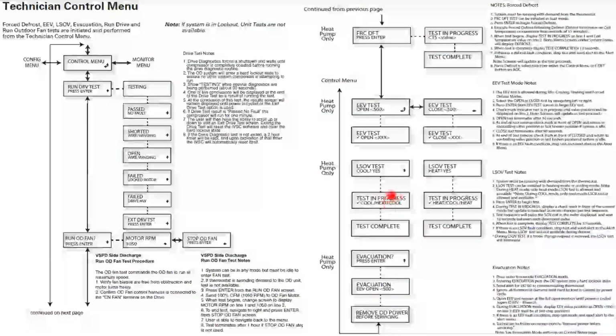And then it'll display test in progress, test complete. If we have to do a pump down and get the refrigerant back into the compressor by closing the liquid line and pulling all that refrigerant back in, we can do that. What it's going to do is open all the EEVs, including indoor EEV2, so we can go ahead and get all the refrigerant back into the compressor.